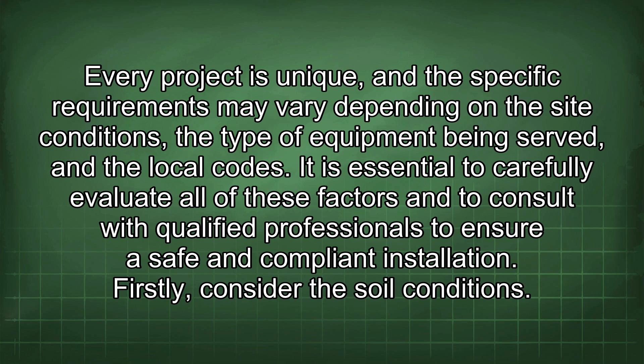Different types of soil have different thermal properties and can affect the heat dissipation of the conductors within the conduit. In areas with poorly draining soil, it may be necessary to use a larger conduit or to derate the conductors to prevent overheating. Secondly, assess the environmental factors. In areas with extreme temperatures or corrosive conditions, it may be necessary to use a special type of conduit or to provide additional protection to prevent damage.